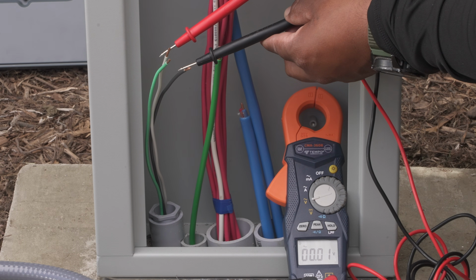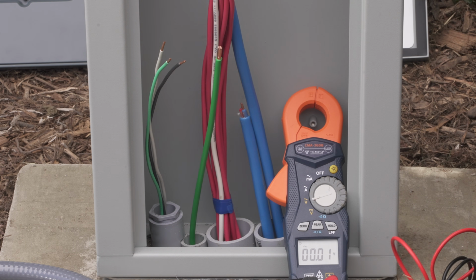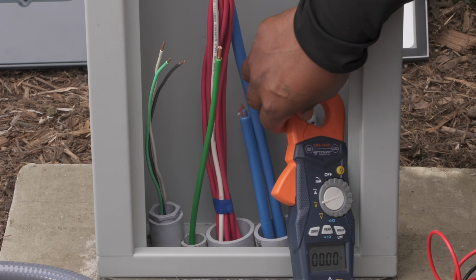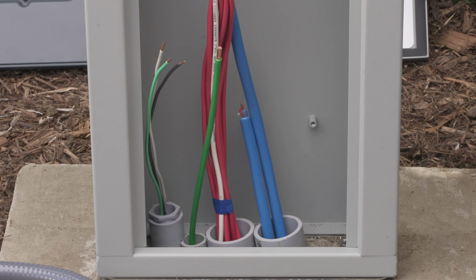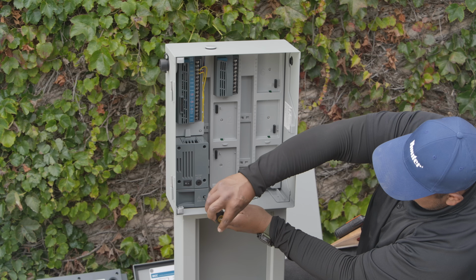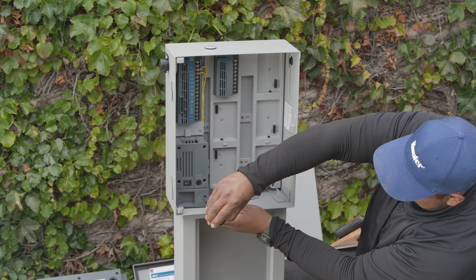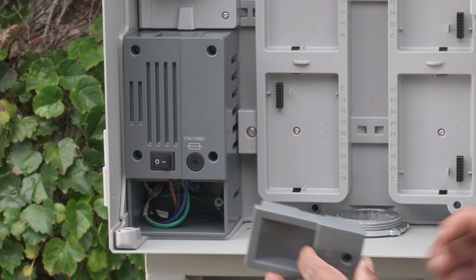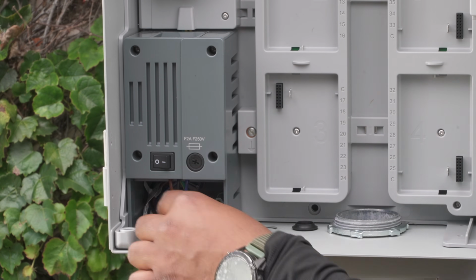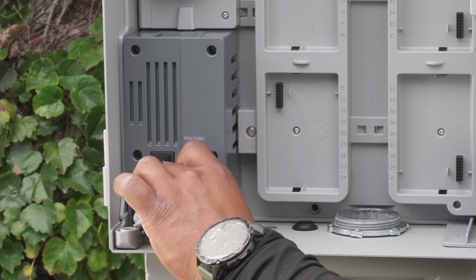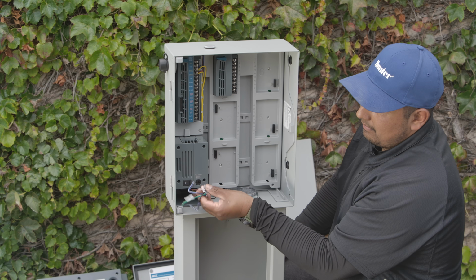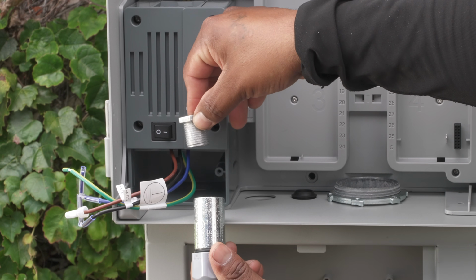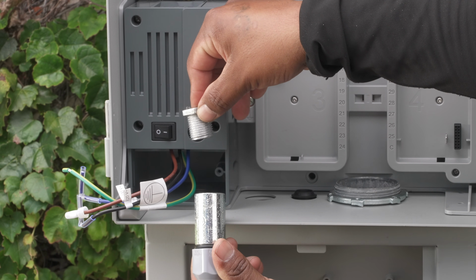In some markets, a licensed electrical contractor is required to make the following connections, and this is the installer's responsibility. Use a number 2 Phillips screwdriver to remove the wiring compartment cover. Withdraw the wires from the transformer to access them during the next steps. The AC conduit opening is designed for a 1/2 inch or 12 mm female threaded conduit nipple.